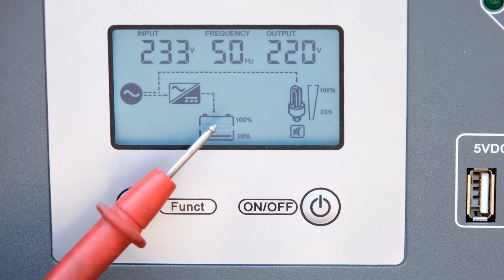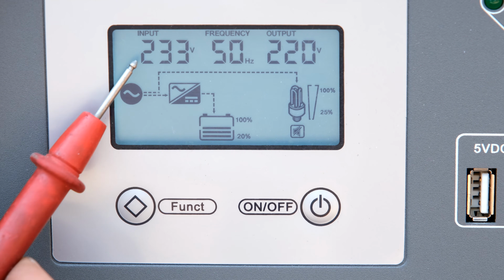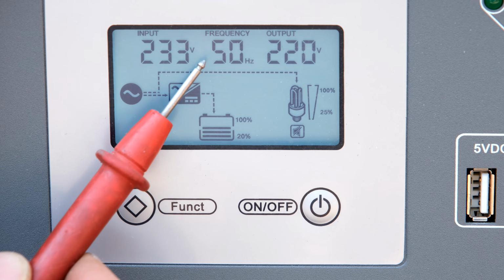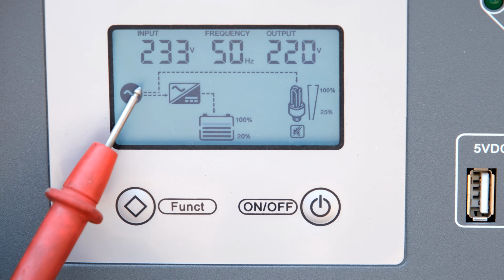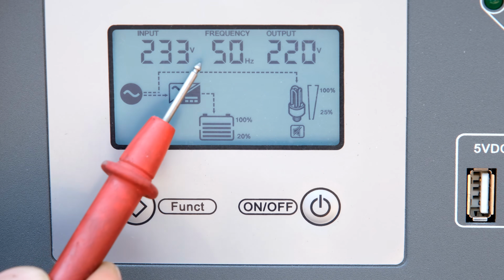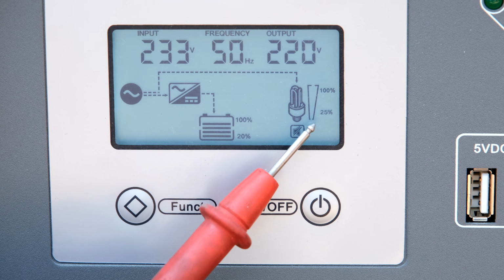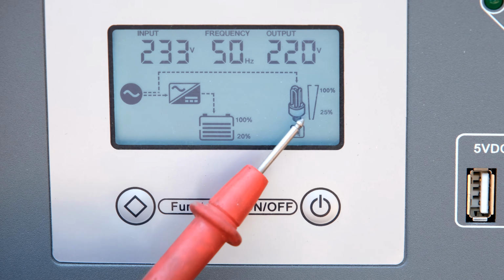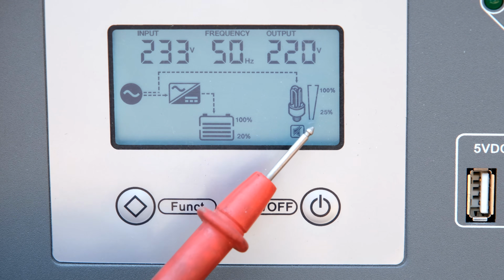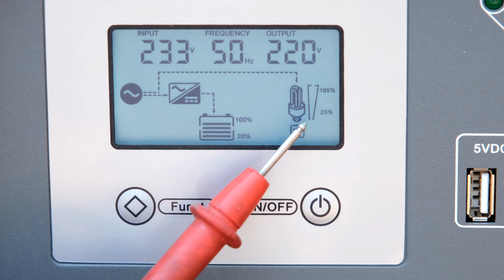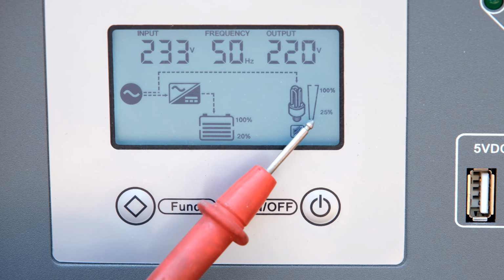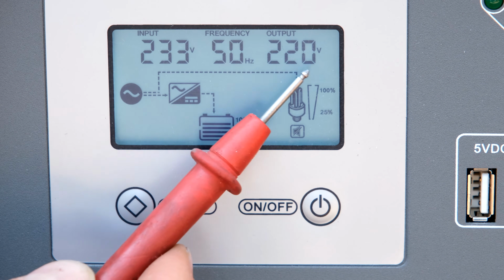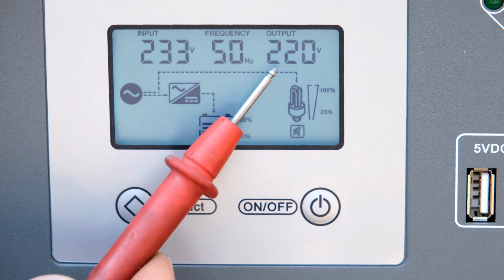So there we can see it is currently in the charging mode. It's fed with 233 volts from the utility, the frequency is 50 Hertz. But notice here, the dotted line goes from there all the way over to the load. The load is currently very low because I only have an LED floodlight of 50 watts connected - I haven't connected that grill yet. But it says here, output is 220 volts.